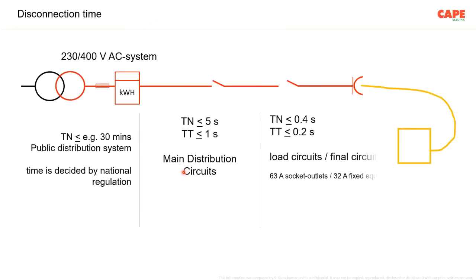This 5 seconds comes from the disconnection time. Disconnection time is established in the standard. You can see here, TN system. First of all, there is an electrical network. There is a transformer. As I told, I am talking about a 230, 400 volt system. Kilowatt hour meter means the point of commencement of supply. Up to the kilowatt hour meter, it is the scope of the electricity supply company. If you have a public distribution system, of course, if you have your own transformer, then from the high voltage side onwards, it is under your scope, applicable for industrial and commercial premises.